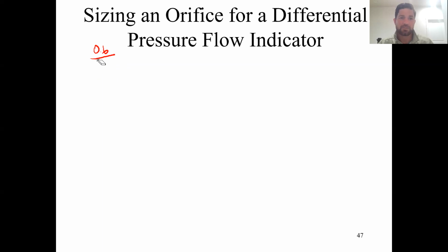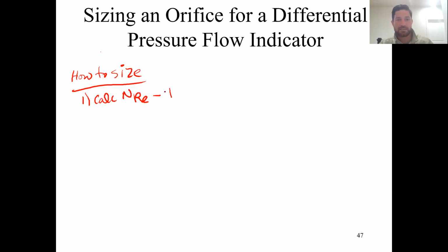Okay, at least work the homework problem that works through this, and that'll give you a little bit of an idea how to do it. So how to size, and this is my process, and it's kind of fail-safe. It mostly works. The first step is calculate the Reynolds number, and this has to be turbulent flow.